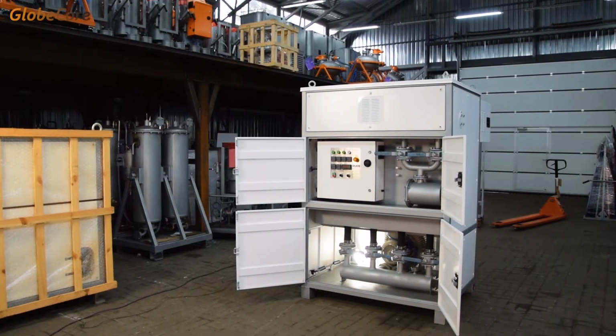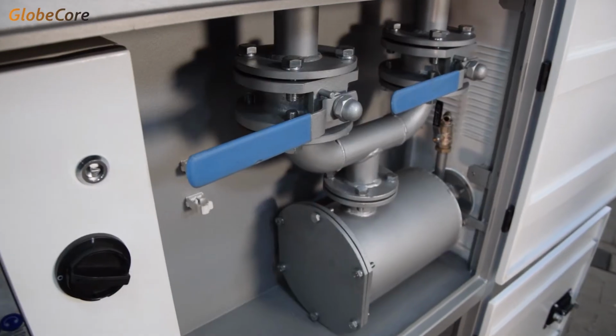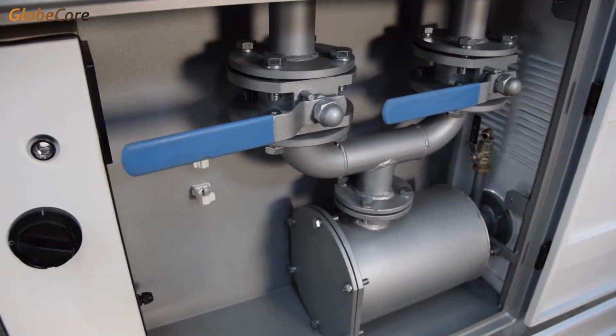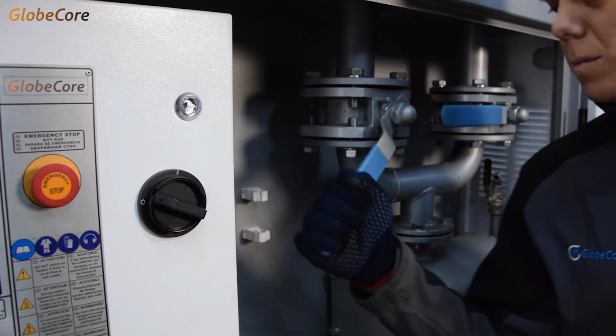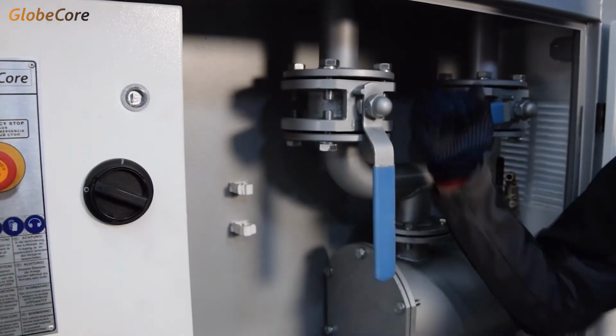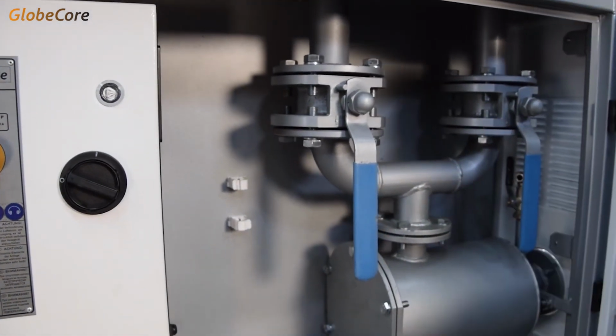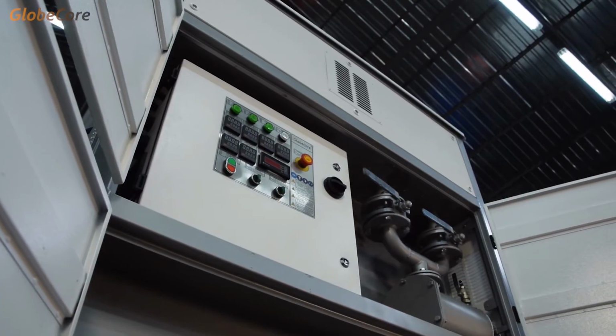The dry filtered air from an adsorber and a particulate matter filter is pumped through the transformer tank, facilitating a flow of fresh air to the maintenance personnel inside and preventing atmospheric moisture ingress to the transformer windings.